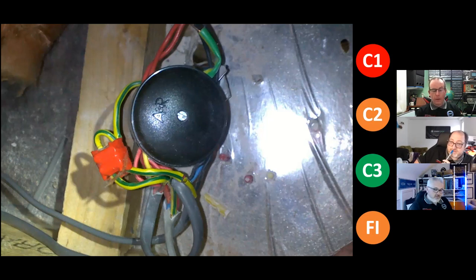They're not skilled. And when you're selecting and erecting an installation, look at Appendix 5. Is the installation under the control of a skilled person who has sufficient skills and knowledge to understand that a single sheathed conductor could give rise to danger through degradation and damage? The fact of the matter is that was covered in insulation. So you immediately have a thermal issue where you can derate the current carrying capacity of the conductor. You've then got section 526, which is your electrical connections, because they're not installed in line with any manufacturer's instructions of that joint box. You've then got the fact that you've got a risk of a rising impedance or a loose connection of a CPC, which is a requirement for safety. So I'm going to go with the C2s.